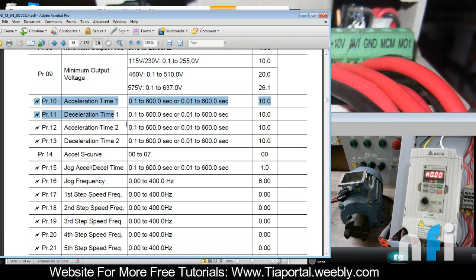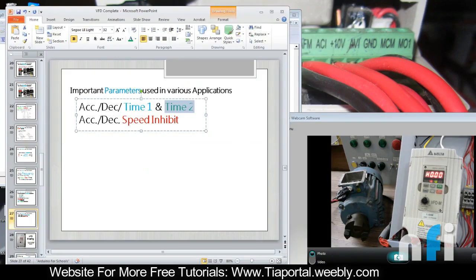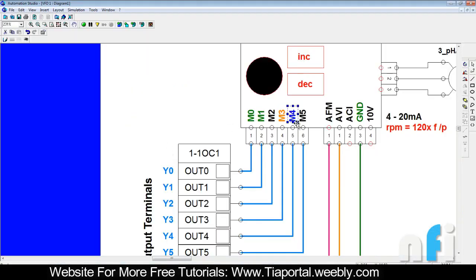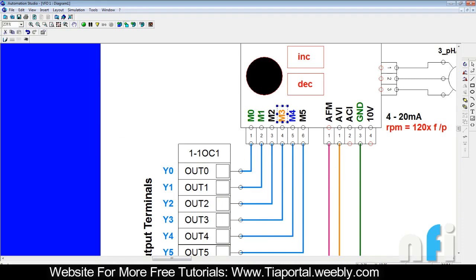We will assign a function to one of these terminals, let's say M3, to work as second acceleration. If I give ground to M3 it will switch over to second acceleration time; if I don't give ground it will roll back to the first one. To assign this function to M3, we'll move to parameter number 40 and enter 11.